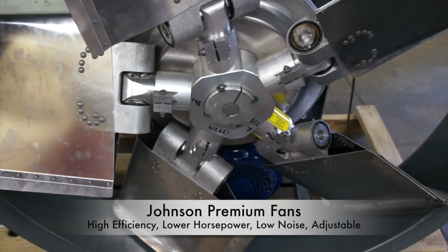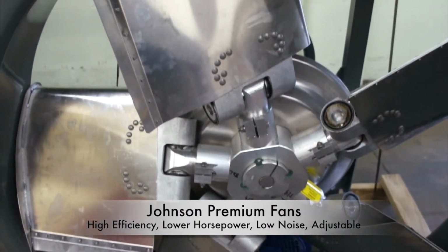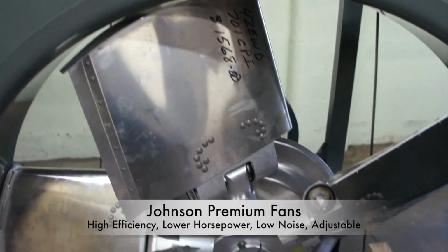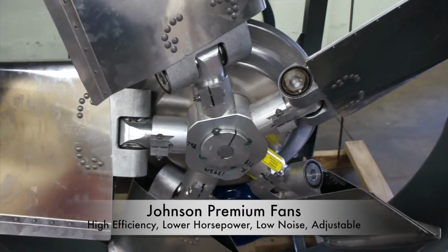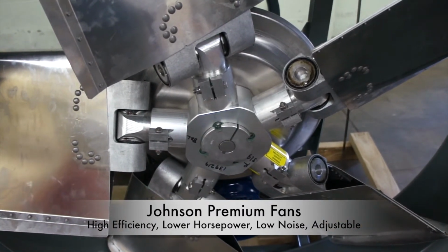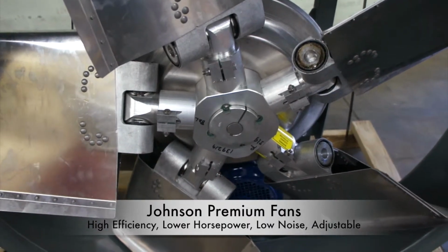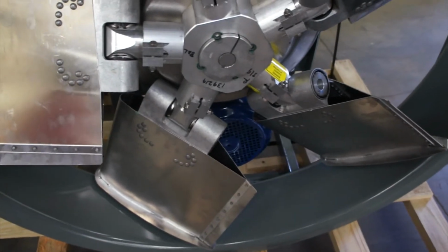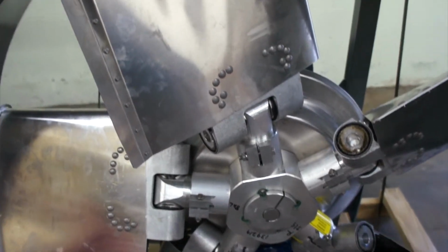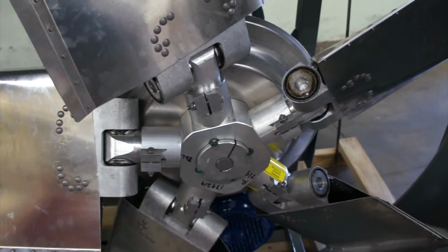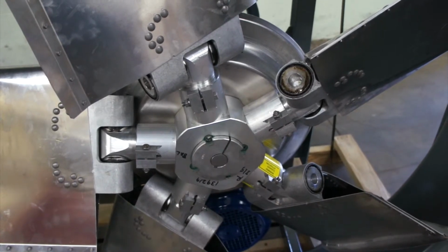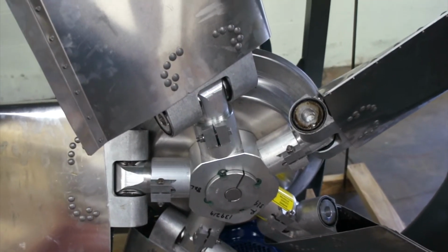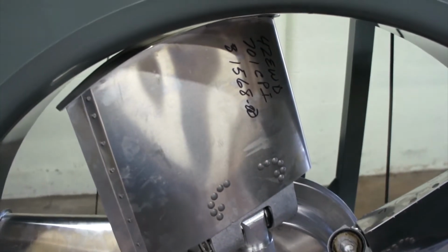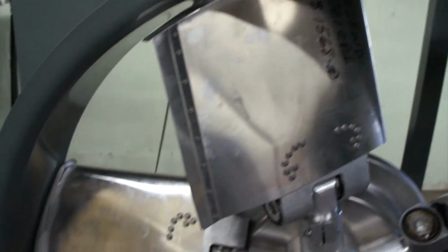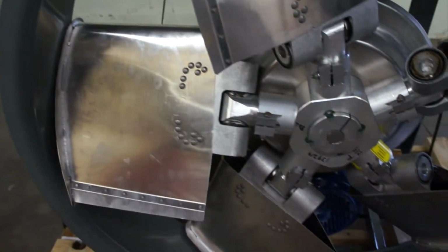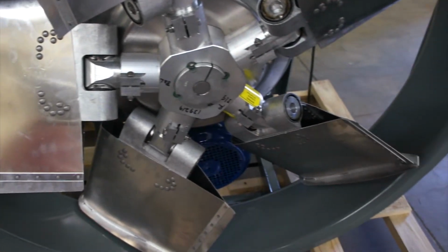This is Johnson Air Rotation Premium Fan. These are the fans that we use in our air rotation cooling units. A couple benefits of these fans as opposed to a standard fan is that these fans operate with less horsepower at comparable static pressures. So for a cooling unit, you have an additional pressure drop that's not accounted for in standard heat-only units. These fans will operate well and at a lower horsepower than the standard unit. Because they have lower horsepower, we do use less utilities. So there's a calculated energy savings using these fans.